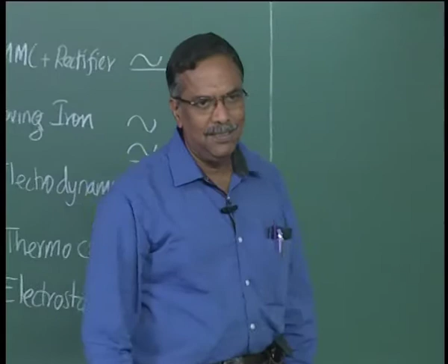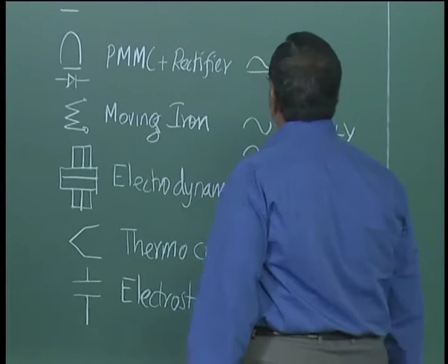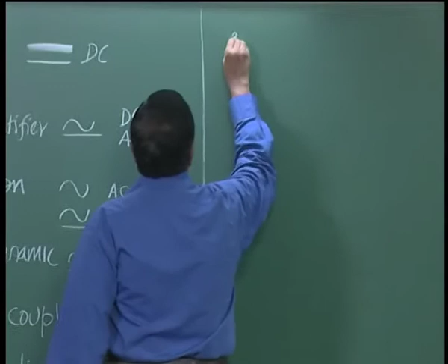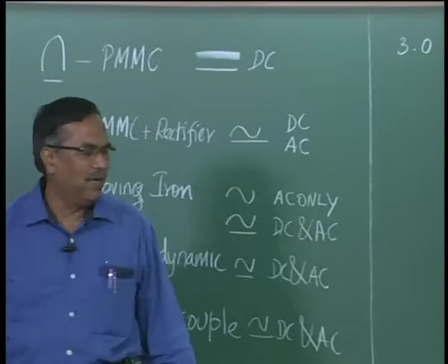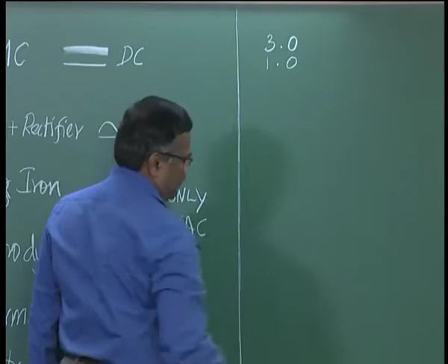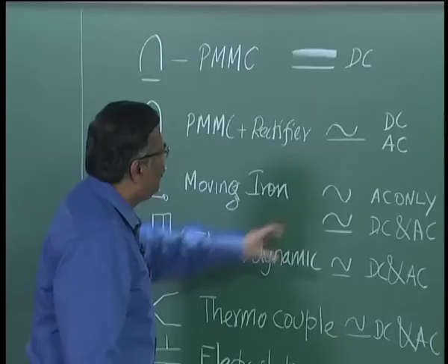So the first symbol that you will see on a meter would be one of these symbols to tell you what type of meter it is. Then the second symbol you would see would be a number, something like 3.0 or 1.0. So we have this symbol followed by this symbol, and the third symbol will be the number. The number indicates the accuracy class of the instrument.